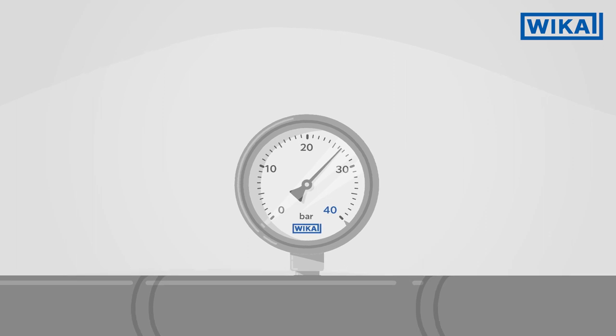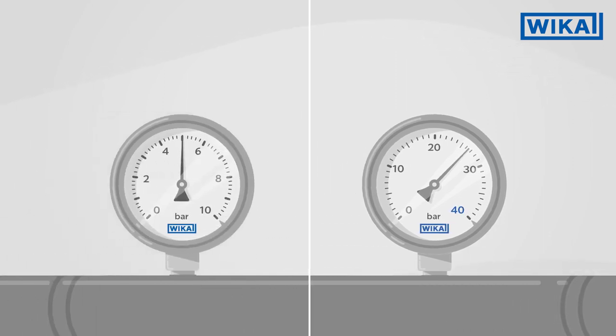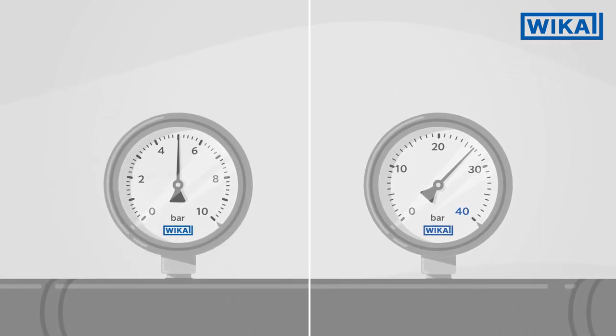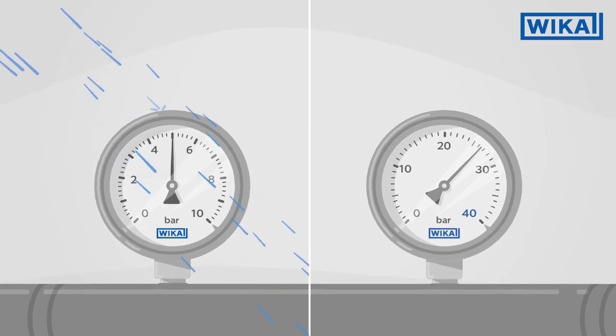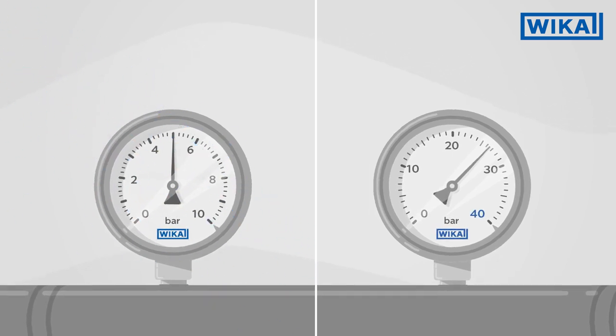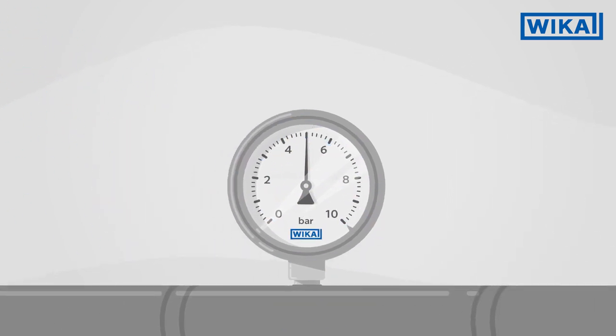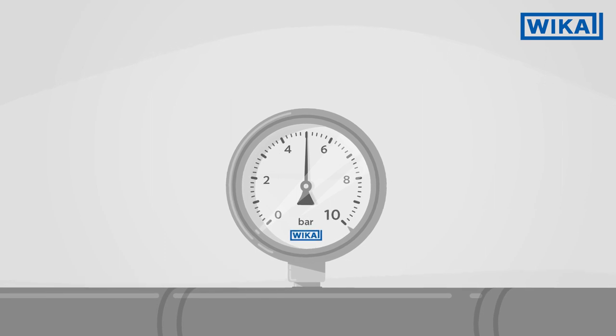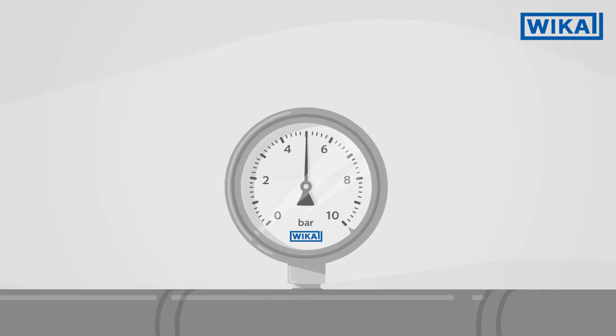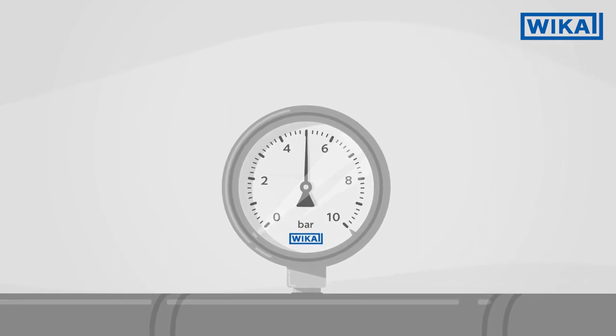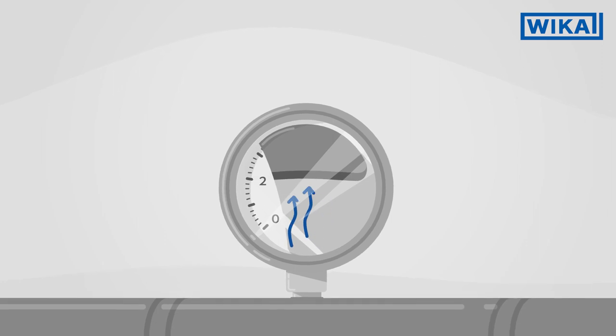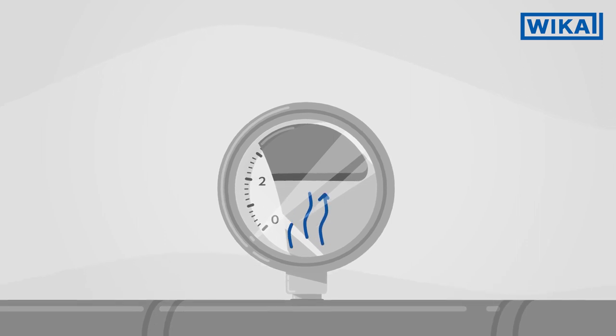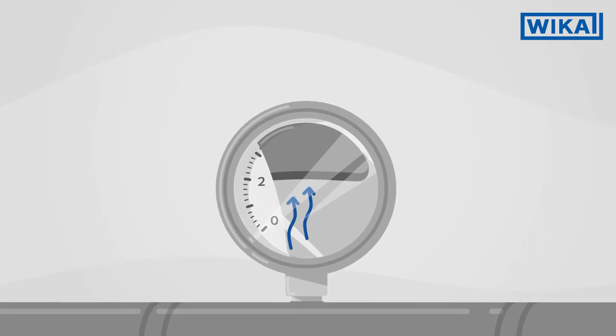It is also not needed if the instrument must be hermetically sealed, for example, to prevent the ingress of water into the case. If the pressure range is, in this case, less than 16 bar, the required compensation is achieved via a pressure compensation diaphragm on the inside of the rear wall of the case.